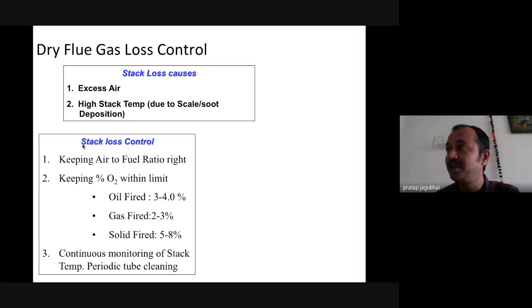This is a combination of the ambient air which we are delivering inside the furnace, which takes part in the combustion, but this ambient air is getting hotter and making the stack temperature hotter and leaving through the chimney. So this higher temperature is a loss of heat. The difference between the stack temperature, the chimney temperature, and the ambient temperature: the higher the difference, the higher the loss available for the dry flue gas.